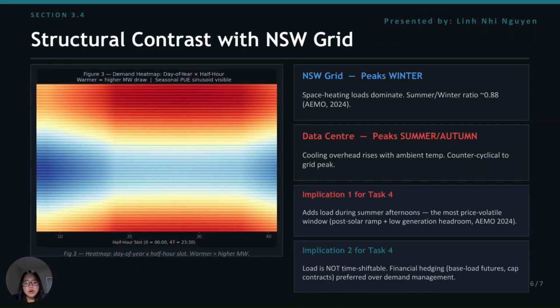So the New South Wales grid peaks in winter for space heating. Our data center is the opposite, highest in summer, as PUE rises with ambient temperature. That means the facility has peak load in summer afternoons, the most volatile window in the NEM. Because DC load cannot be deferred, financial hedging is the preferred strategy over demand management, which leads directly to task 4. Thank you.